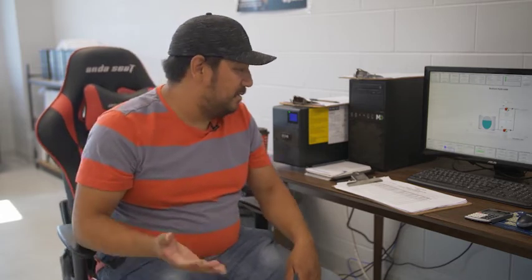So when I'm noticing 100 cubic meters of water being used, I'm also noticing our distribution pressure has dropped at the same instance. So again, that's a red flag. We get on the horn, we let everybody know, hey, we think there's a water leak somewhere. We've lost this much water, where normally we're only pushing 200 cubes, where yesterday we pushed 300 cubes. Again, maybe our pressures were usually at 500, where today it's at 460 kPa. So yeah, then there's something wrong there.